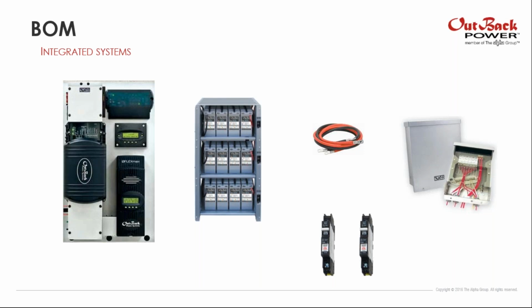A FLEXpower One, the components are an inverter charger. It has two FLEXware 250. Those FLEXware have inside, the DC one has a GFDI breaker, a PV array breaker, the battery breaker, a charge controller. It has this kind of conduit. The AC FLEXware have the inverter input, output, and bypass. We have a FlexNet DC, a Hub 10, Mate3S, and a FlexMax FM80.